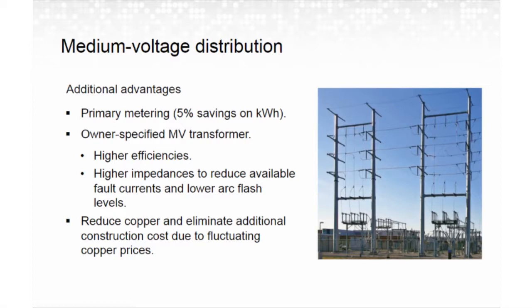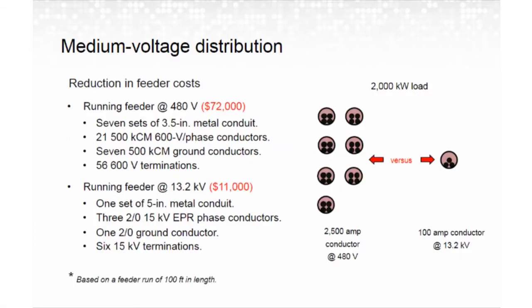Now, increasing the system voltage decreases the current and thus decreases the losses in material costs, as Ken has previously given some examples for. Now, when the client controls the transformer selection at the service, the efficiency and the impedance can also be chosen. Now, utility companies may choose to select lower impedance transformers in order to save them energy and losses. But that happens at an increase in cost of the client's electrical distribution system, as I discussed previously, with available fault current impacts for arc flash and selective coordination and SCCR. Now, when you're deciding to distribute at the utility supply voltage, discussions about who is going to own the medium voltage equipment and switchgear will be required, as that also has an effect on what the owner is going to have to pay to take advantage of some of these savings.